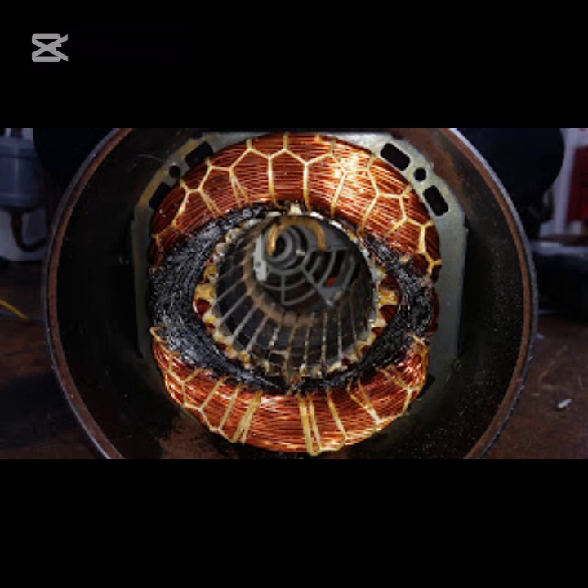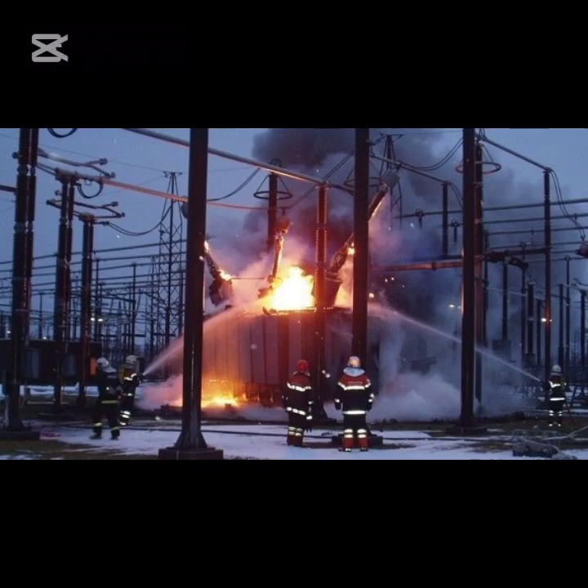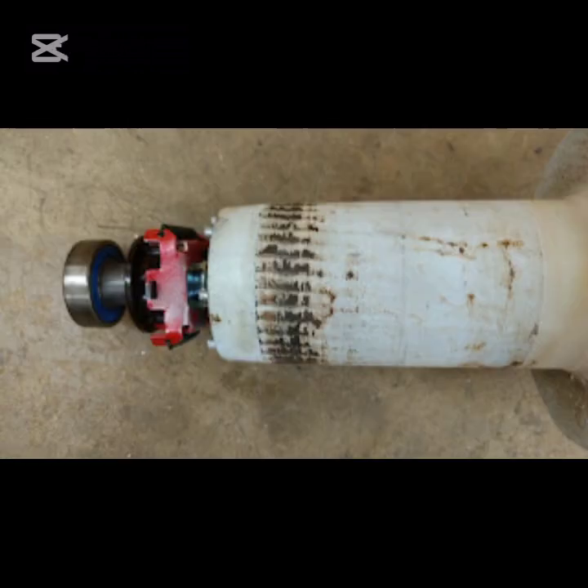Number 1. Overheating. Excessive current flow during a short circuit can cause significant overheating in electrical equipment. This can lead to insulation damage, component failure, and reduced equipment lifespan. Number 2. Equipment damage. Short circuits can cause extensive damage to electrical equipment, including transformers. It causes winding damage and insulation failure. For generators, it causes stator or rotor damage. For circuit breakers, it damages contacts and causes operational failure.